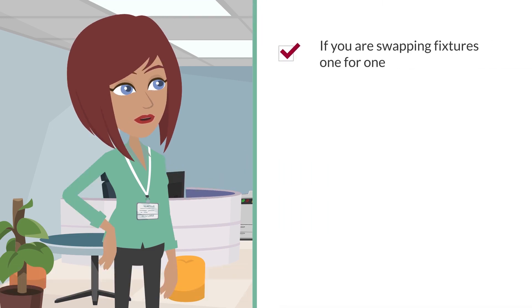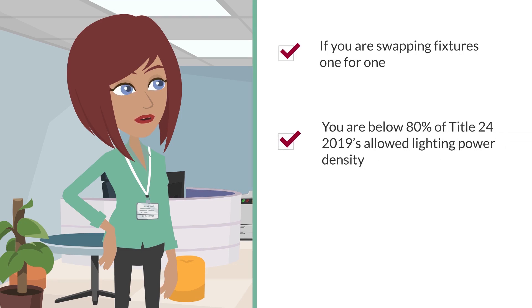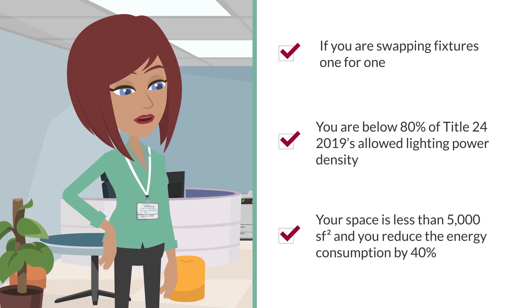1. If you are swapping fixtures one for one. 2. You are below 80% of Title 24 2019's allowed lighting power density. 3. Your space is less than 5,000 square feet and you reduce the energy consumption by 40%.